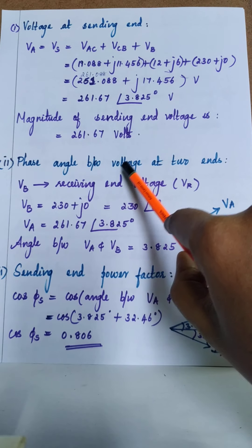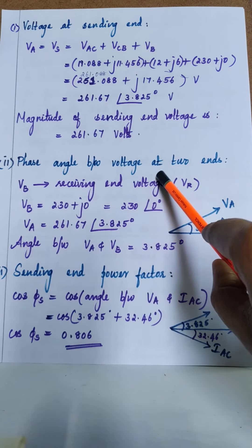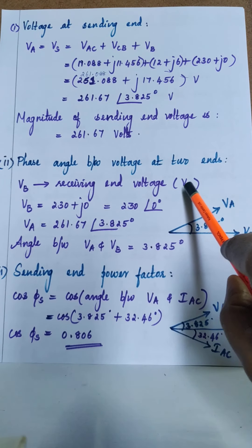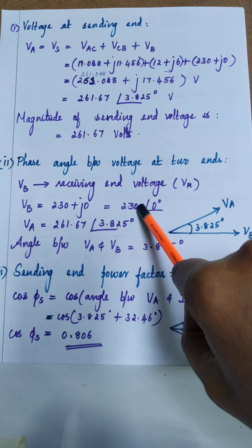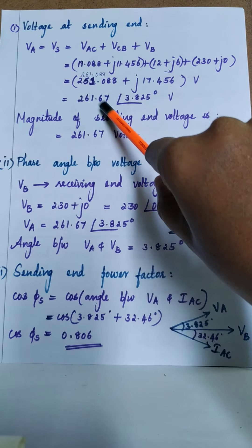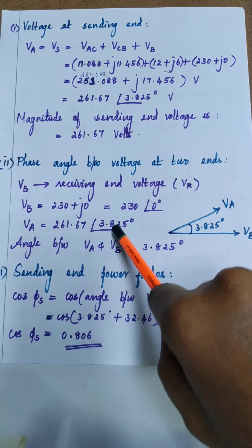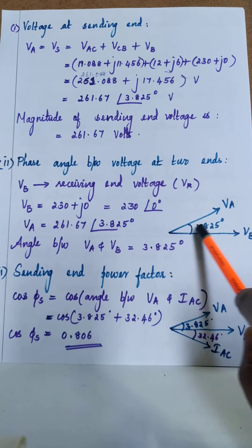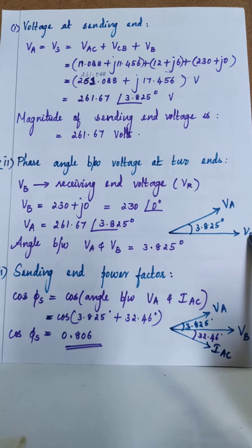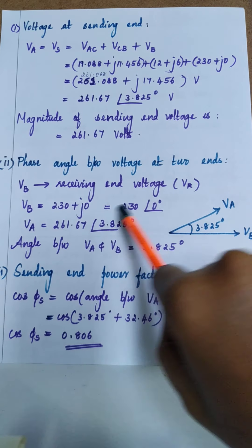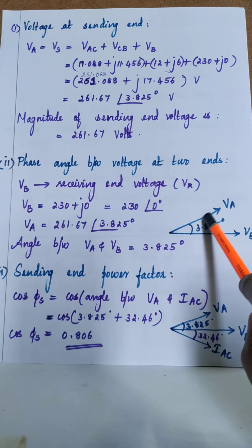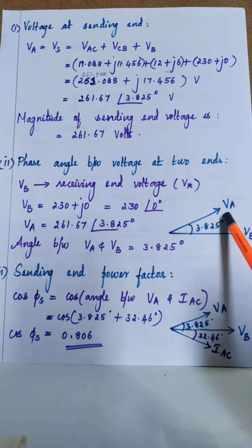The second part is the phase angle between voltages at the two ends — that is, the angle between sending end voltage and receiving end voltage. The receiving end voltage VB is taken as the reference, so VB = 230∠0°, and the sending end voltage VA = 261.67∠3.825°. The angle between VA and VB is therefore 3.825°. In the phasor diagram, VA is drawn ahead of VB by 3.825 degrees, since the positive angle indicates VA leads VB.